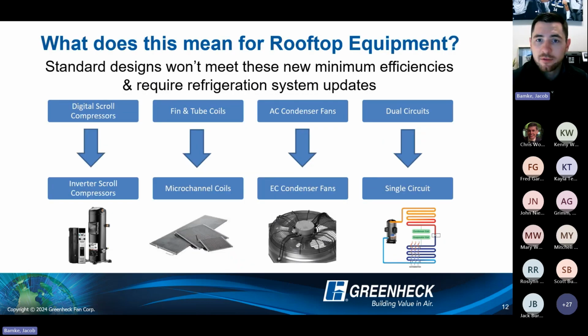At a very, very high level, this is why you're seeing so many changes to all of the equipment from an outdoor air standpoint. So DOAS equipment, rooftop equipment, you're seeing the transition from the digital scroll compressors to the inverter scroll compressors. And that is because inverter scroll compressors are 15 to 20% more efficient at your part load conditions. So digital scrolls, great at capacity control, but they're still always using the same amount of energy, even at your part load conditions, versus your inverter scroll compressors, where you add that VFD, now you slow down the frequency, which means you get energy savings.